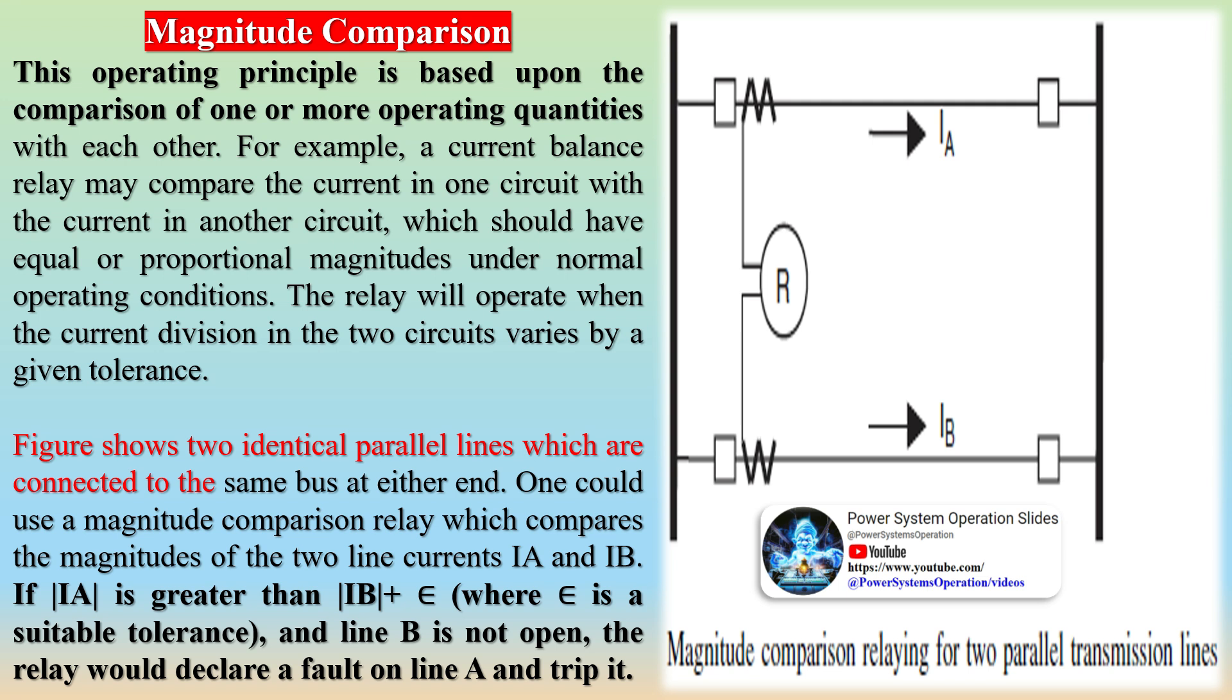The relay should be designed to operate and trip the circuit breaker for all currents above the setting, or, if desired, the relay may be connected to sound an alarm, so that an operator can intervene and trip the circuit breaker manually or take other appropriate action.